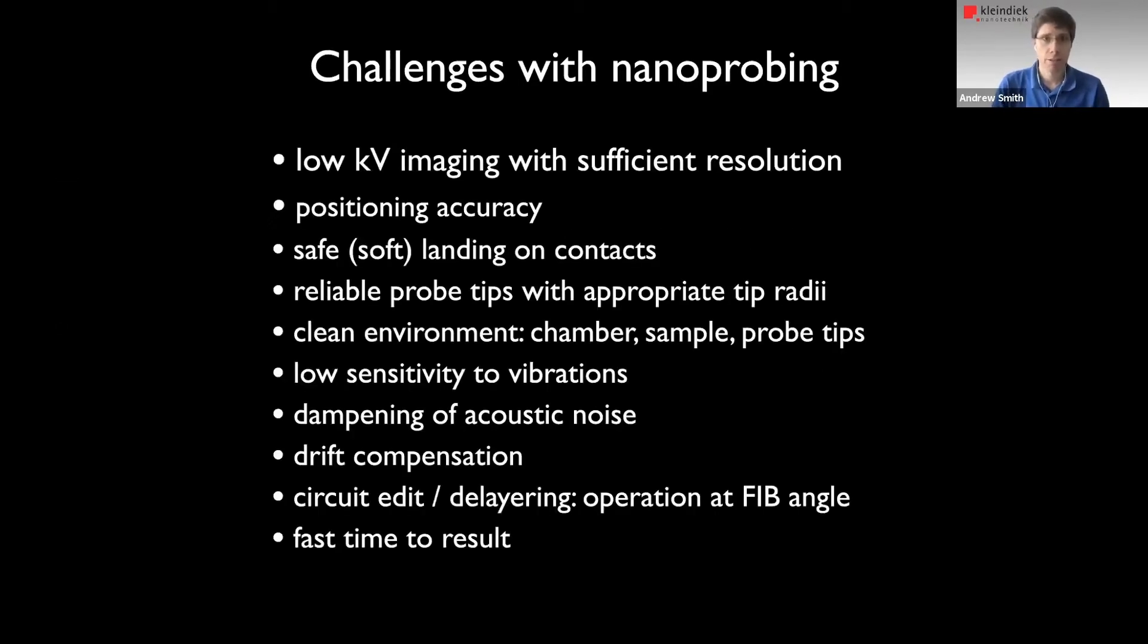Beyond that, there's more challenges that we have to address. We need to be able to accurately position the probes. That's obvious. We need to be able to gently land them. We need a clean environment. We need to worry about vibrations and noise. Drift, as we saw, is an issue. And of course, operating at tilt angle is a plus because we can do things like circuit edits and also expose the contacts we want to address using delayering. And of course, most important of all, we need to get the samples in and out of the chamber as fast as possible so we get a nice process flow.